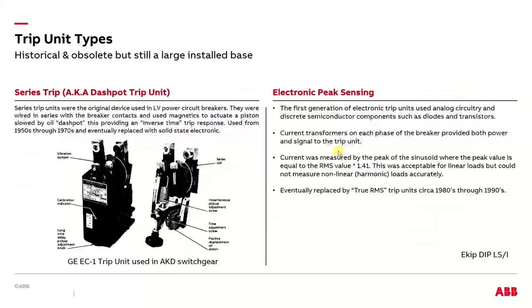Okay, I wanted to touch on this really quick. These are some historical trip units, and a lot of them are gone, but I'm assuming a lot of you are EasyPower users and are in the industry, looking at existing facilities, and they still exist out there. There's the series trip, also called the dashpot trip unit, and those were installed in power circuit breakers from the very inception. So it's basically a switchgear trip unit.